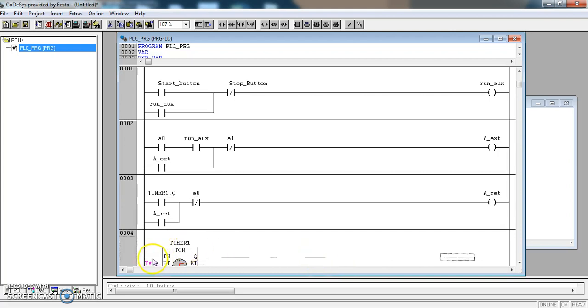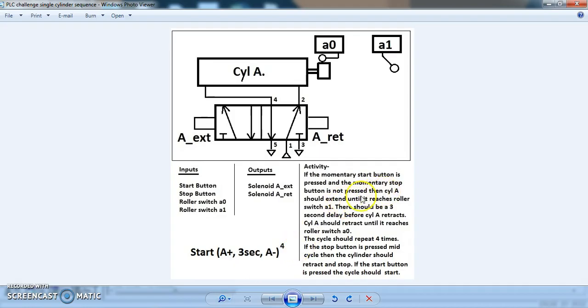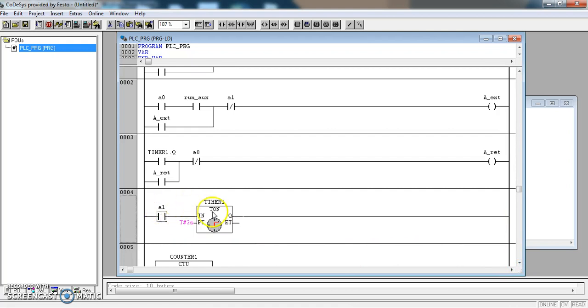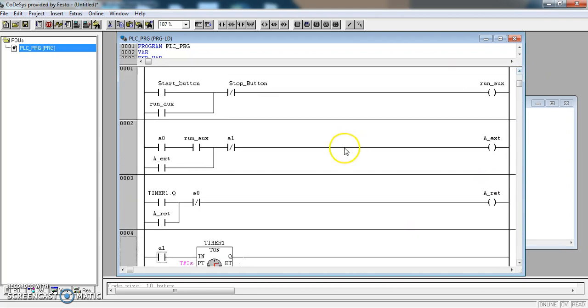The timer needs control, so I will add a normally open contact here. If we go back and have a look at our system again — cylinder A should extend until it reaches roller switch A1, so A1 is what triggers and starts the timer. Going back to the program, A1 is what should start the timer, and that should control our timer. When A1 becomes active the timer will start to count. After 3 seconds it will turn on the Q value, and the Q value will then start the cylinder retracting.